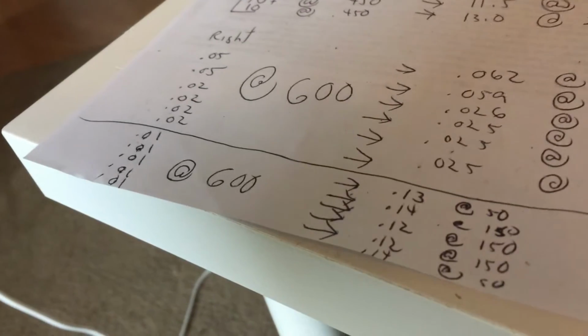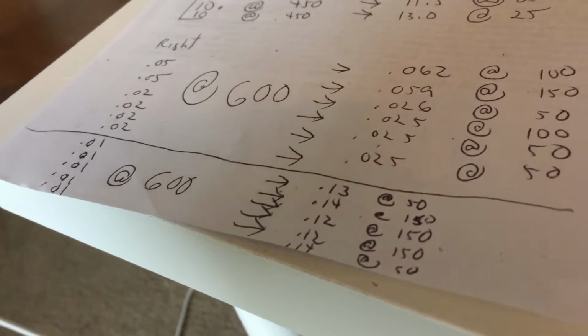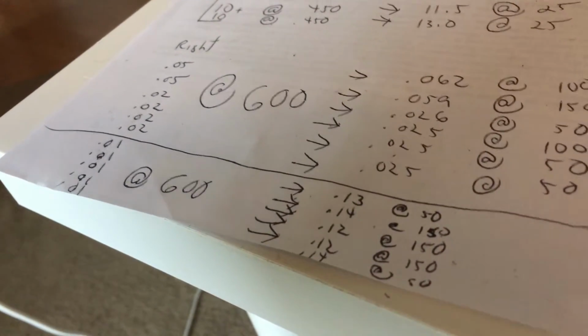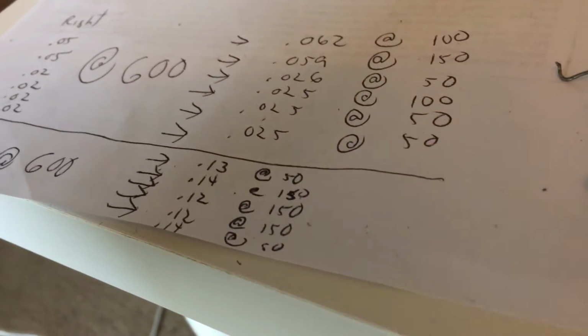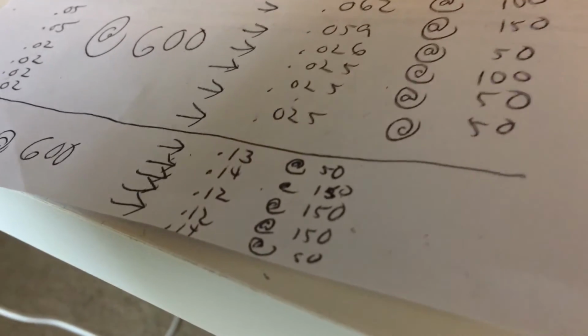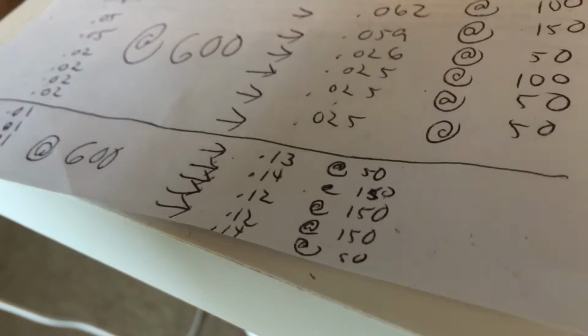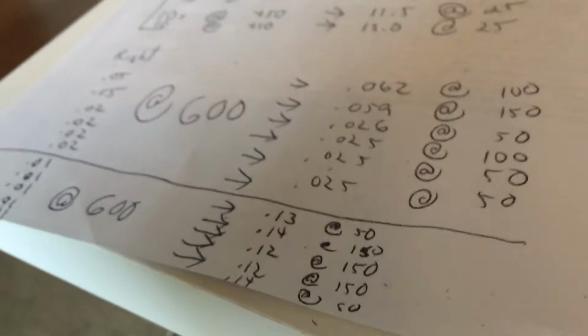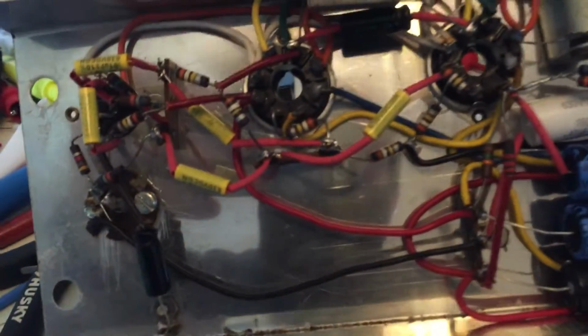The ones on the left that were pulled out exhibited the same qualities as the other ones. The actual values weren't far off, but the leakage and breakdown voltage were quite low, ranging from 150 down to 50 volts. So this concludes the capacitor swap-out portion.